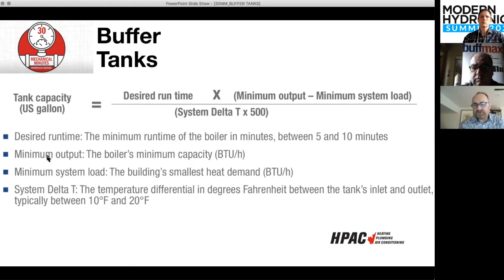So what if I've got a modulating boiler? What's the minimum firing rate that boiler can ever run at? If I've got a 100,000 BTU boiler that's got a 10-to-1 turn down ratio, which is very good, the industry standard used to be 5. Now we've got a lot of boilers that can do 10-to-1. So that means it can run at 10,000 BTUs. My boiler can fire as low as 10,000 BTUs, so that's why I want to look at that minimum firing rate.